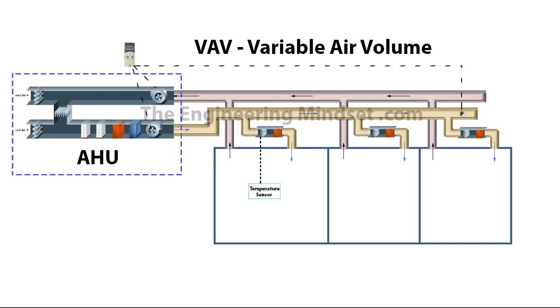And this will reduce the amount of air being pushed into the duct. The pressure sensor is set with a set point of where it should be operating at, or what that pressure should be at that end of the duct. And the fans will reduce in speed to reduce the amount of air being pushed into there to match that pressure point.